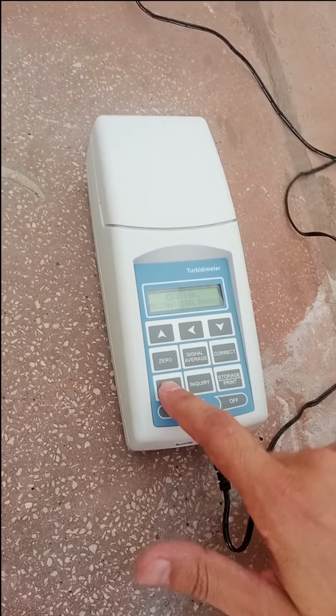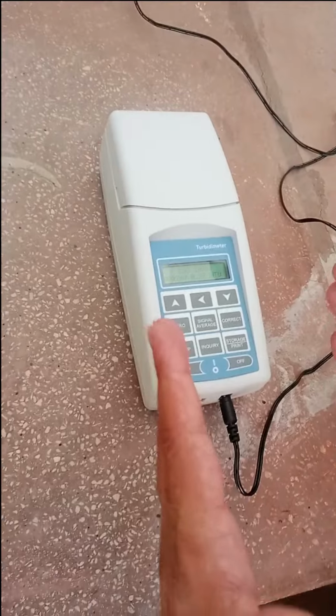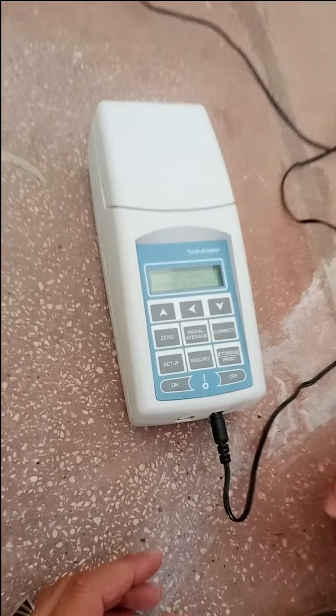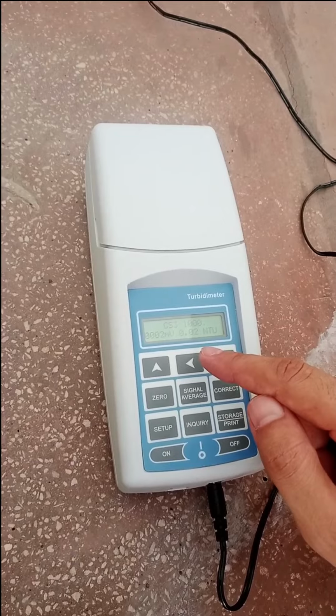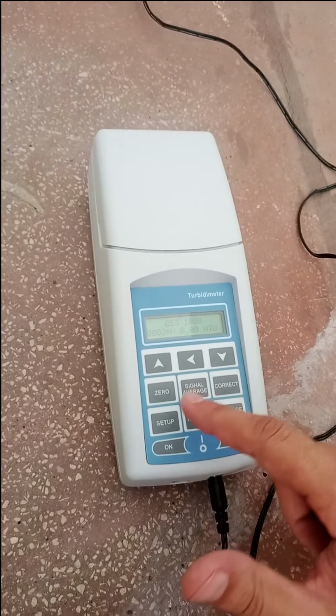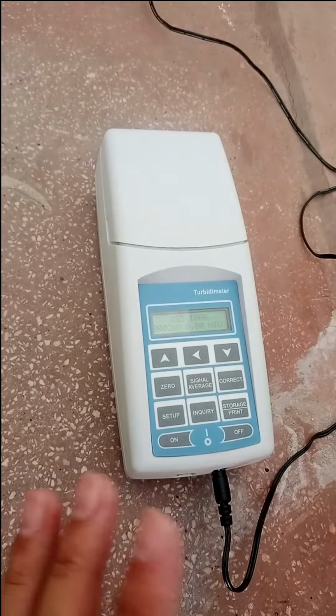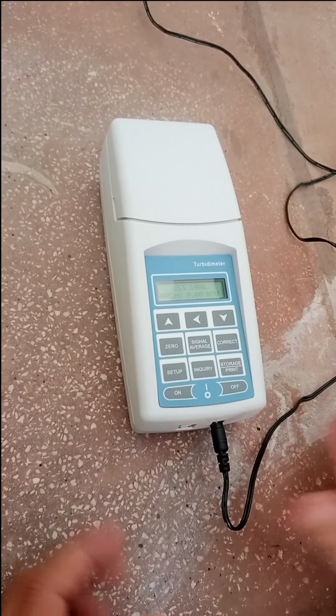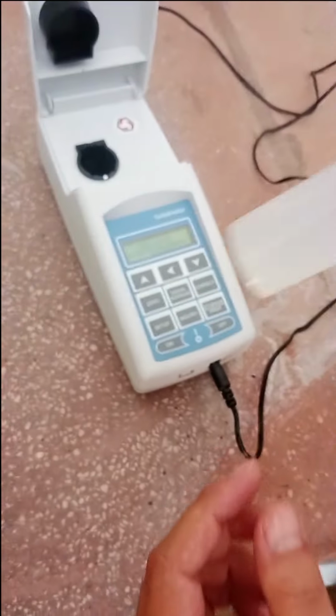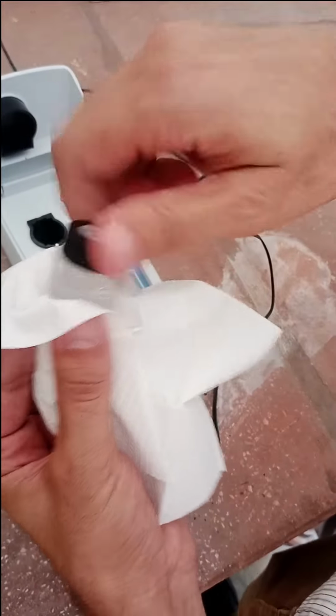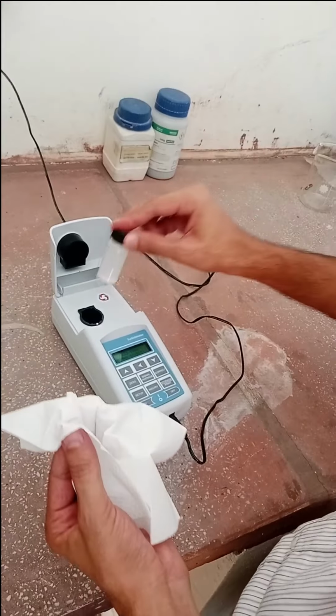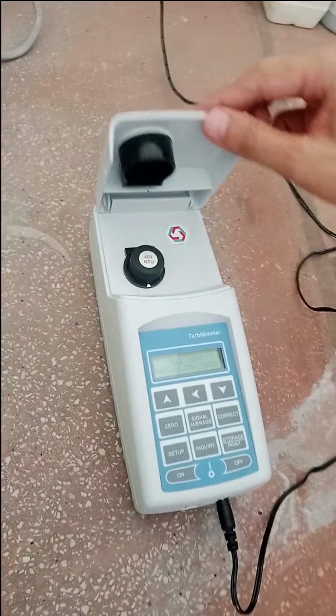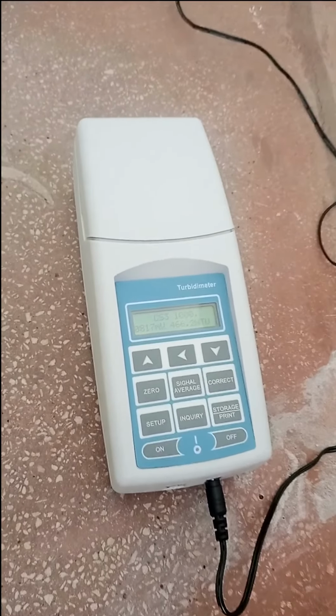We will go through CS1, CS2, and CS3. In CS3, we can measure values from 101 to 1000. The value will stabilize to 0.00. If it is not stabilized, then you can press the 0 button to make it 0.00 and remove the error. Now we will place the sample, but make sure to clean it with clean tissue paper, because this machine will emit rays, and through those rays it will measure the value. It is suggested to shake it well before placing it in the chamber. So now we will wait for the values.